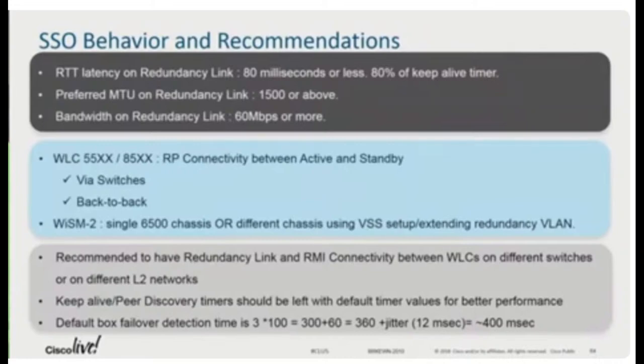One last thing to always keep an eye for: when you have that redundancy link, and you have two controllers deployed in two different buildings, make sure the round trip time between the two is less than 80 milliseconds. Otherwise, if it's more than 80 milliseconds, you'll see a flip-flop happening, where one becomes active, then the other becomes active, and this keeps happening because of the configured timers. So make sure it's less than 80 milliseconds of round trip time between the primary and backup controller.